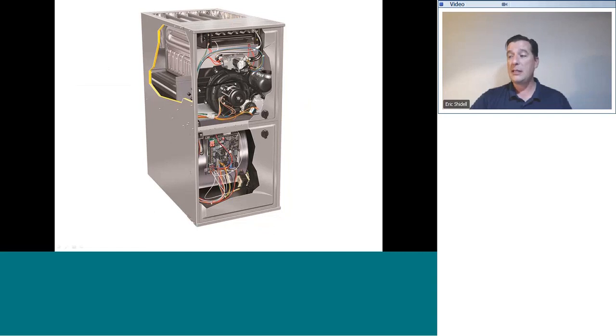Notice that on the condensing appliance, everything from this level downwards, from where that secondary heat exchanger is, is plastic. It's because that condensation is occurring inside of the secondary heat exchanger. So from this point onward, the flue products are cool enough that they're wet and moist. Therefore, all of the material that directs and contains those flue products needs to be water safe, non-corrosive, and therefore it's made of a high temperature plastic.